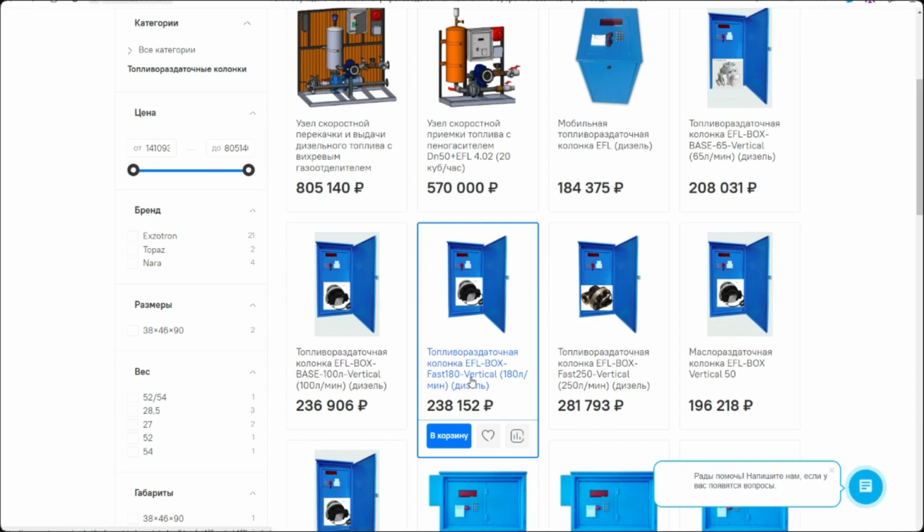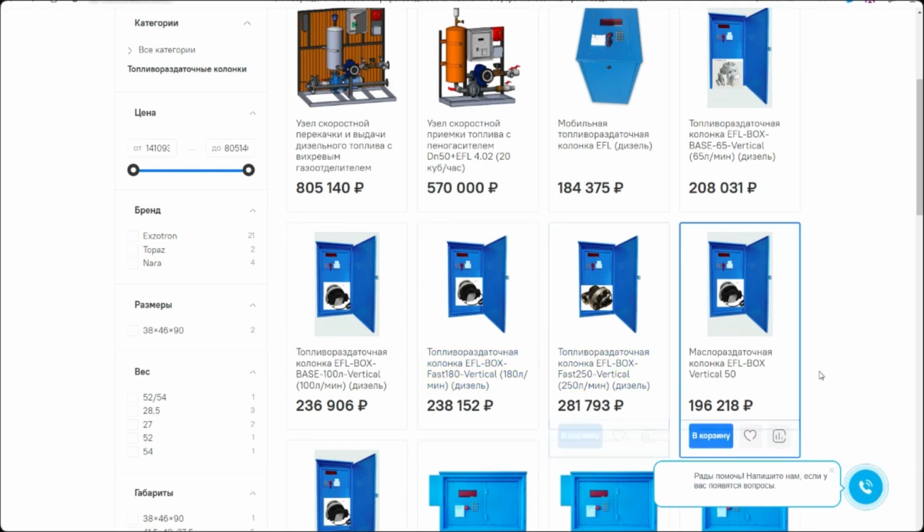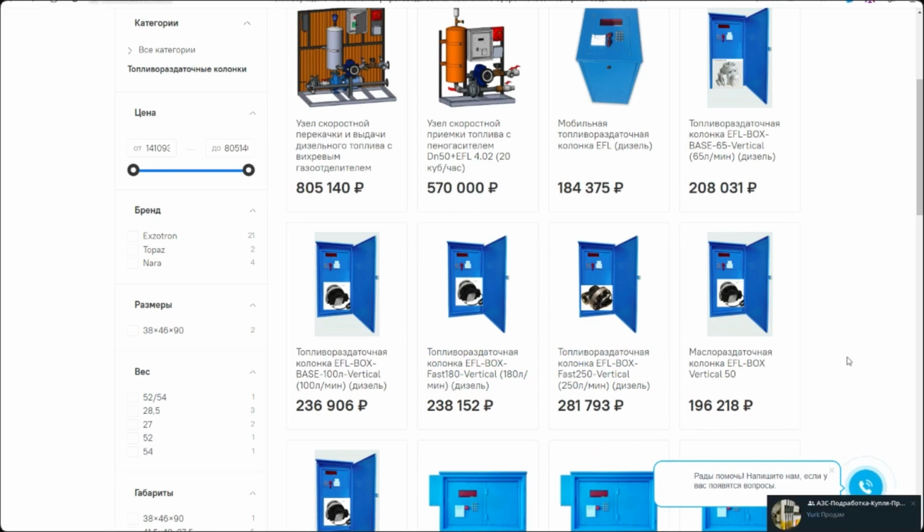Well, then, most likely there are some peculiarities here. So, firstly, probably there is a long tube at the bottom, maybe narrowed, and accordingly you got such an effect. Because we have 180, this is in the standard version. If there is a ground capacity, you can easily connect even 5 meters there. So some even pour more. On the contrary, even 180, they even pour over 200. So in these challenging conditions, she is unable to pump up the pressure because the machine lacks enough power to lift the fuel from the lower area.